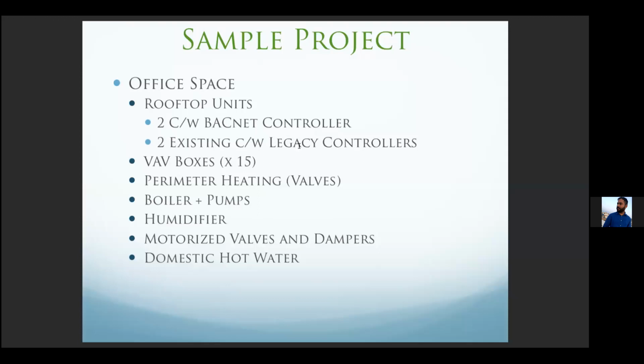Legacy controllers, I need to understand if the manufacturer has a converter that's going to convert their legacy protocol into BACnet. If yes, I'm going to buy that converter and use that converter to point map into my new system. If they do not have such a thing, then what we may want to do is just put a controller, wire it to the terminal strip of that unit, and you may just get the simple 5 wires of the thermostat control and be able to control that unit that way.